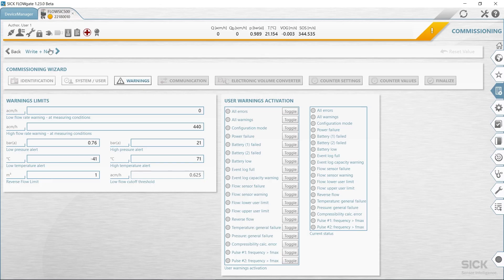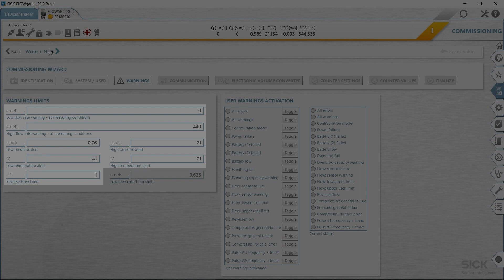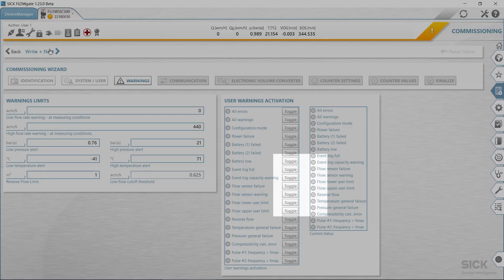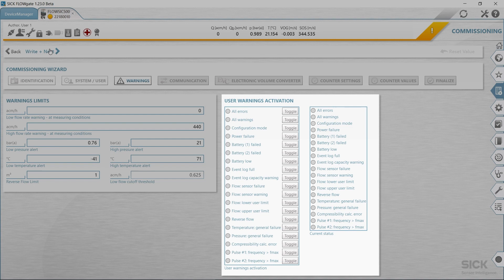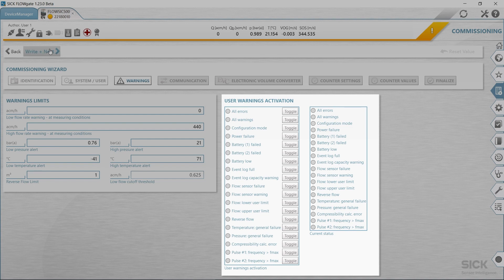If you click on next, you will face the page warnings. Here you can enter or configure different limits for the FlowSIC 500 when it should output warnings or errors. There's a possibility to set limits for flow rate, pressure, temperature, reverse flow volume, and a limit value for low flow rate or zero flow cutoff. In addition, the warnings signaled by the device can be individually activated or deactivated in the user warnings activation area.